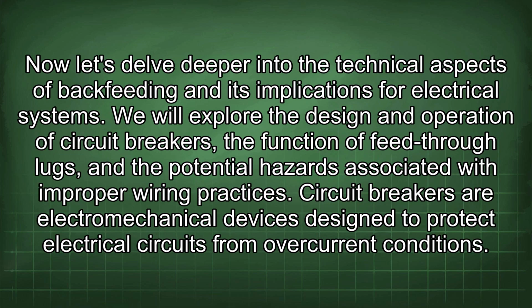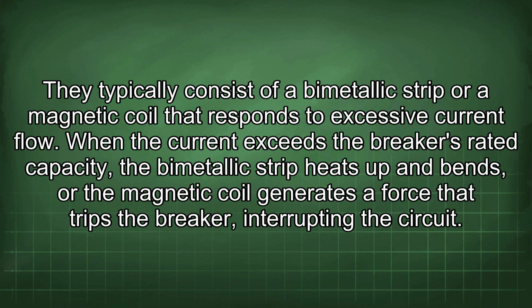Now let's delve deeper into the technical aspects of backfeeding and its implications for electrical systems. We will explore the design and operation of circuit breakers, the function of feed-through lugs, and the potential hazards associated with improper wiring practices. Circuit breakers are electromechanical devices designed to protect electrical circuits from overcurrent conditions. They typically consist of a bimetallic strip or a magnetic coil that responds to excessive current flow. When the current exceeds the breaker's rated capacity, the bimetallic strip heats up and bends, or the magnetic coil generates a force that trips the breaker, interrupting the circuit.